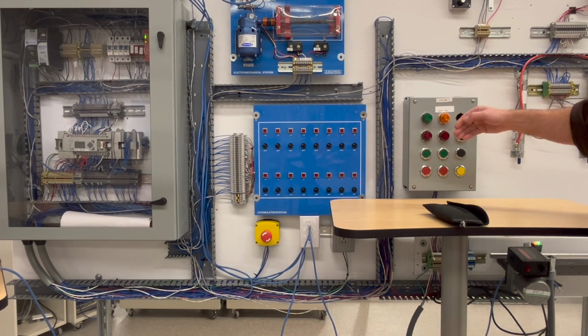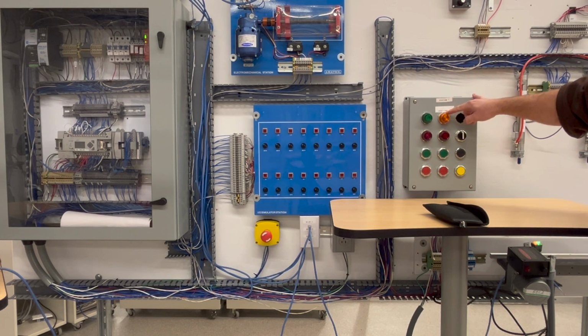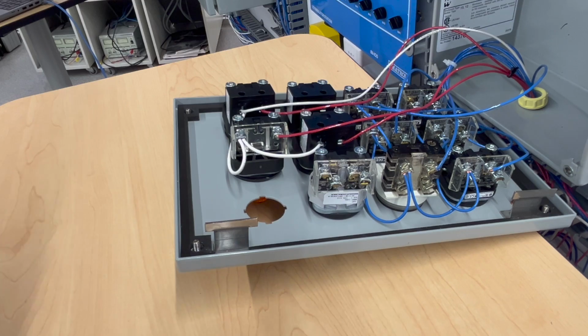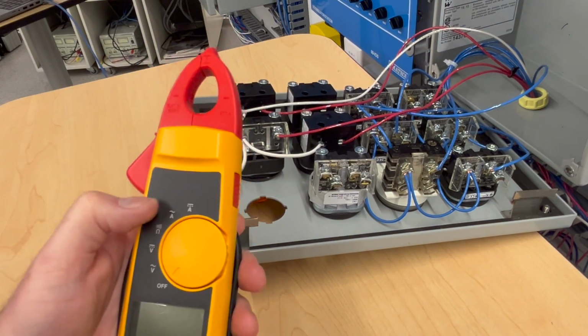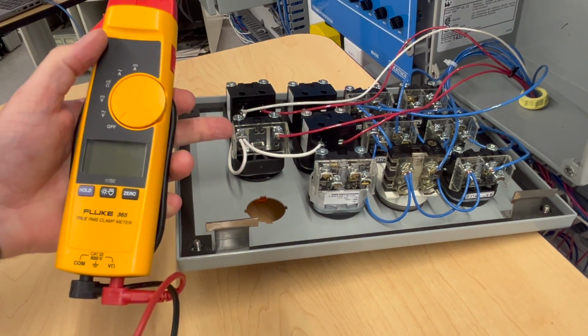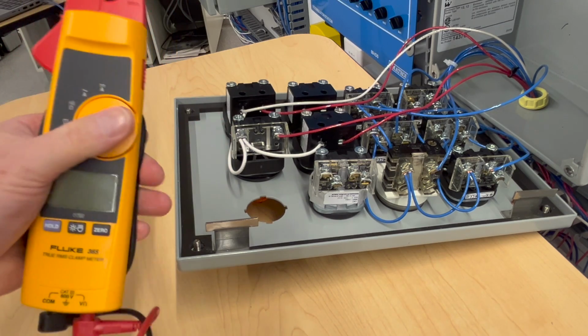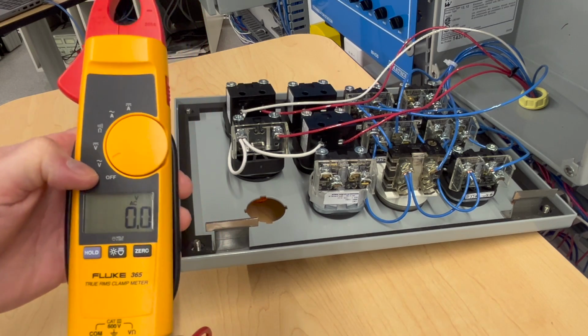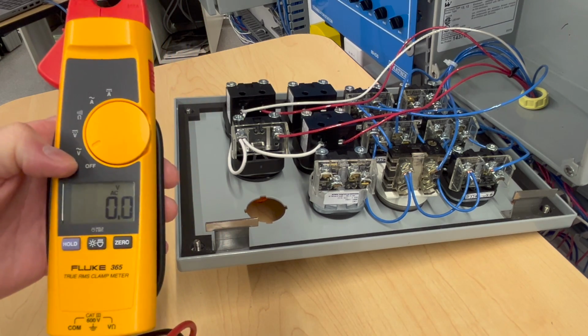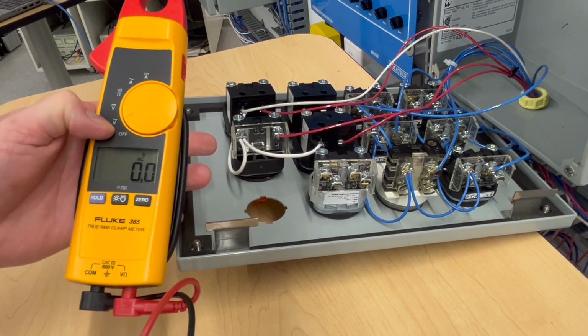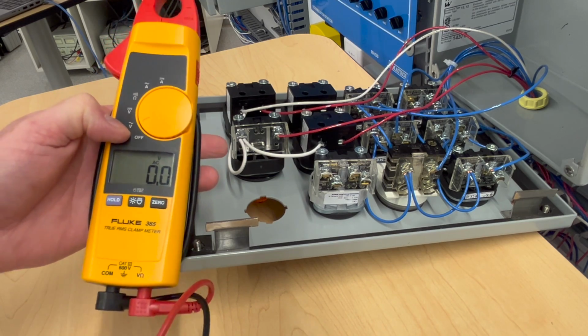So now the next thing we wanna do is we wanna take a voltage measurement off the back of that to see if the voltage is coming in here, which will be our very first step. Okay, so the first thing we're going to do is check voltage back here. So what we're gonna do is turn this to volts AC. Now you need to verify what voltage is going to be present here. Is it gonna be 24 volts DC or 120 volts AC?